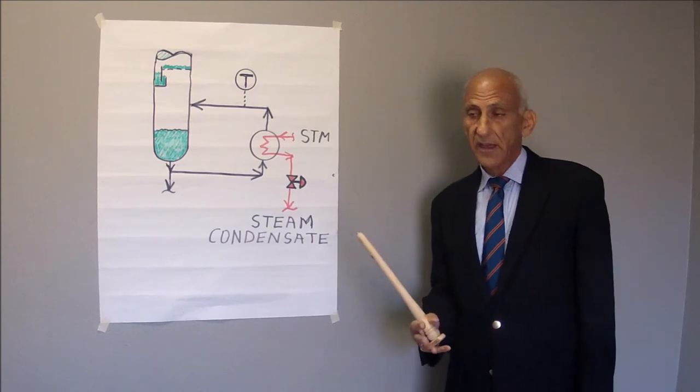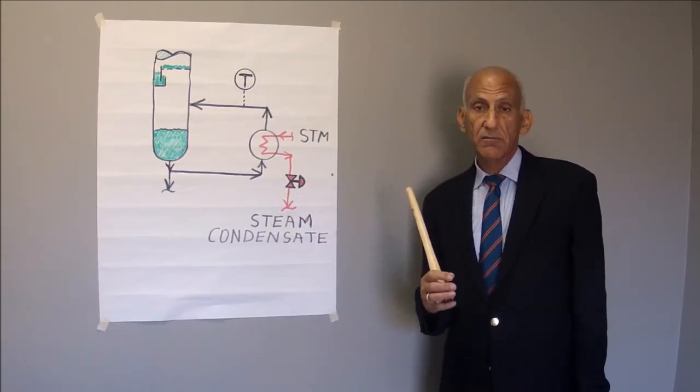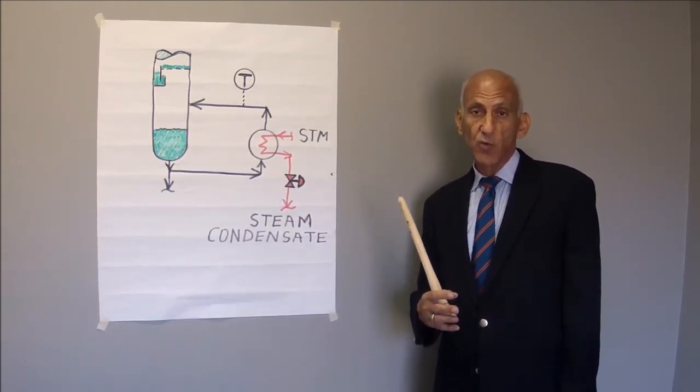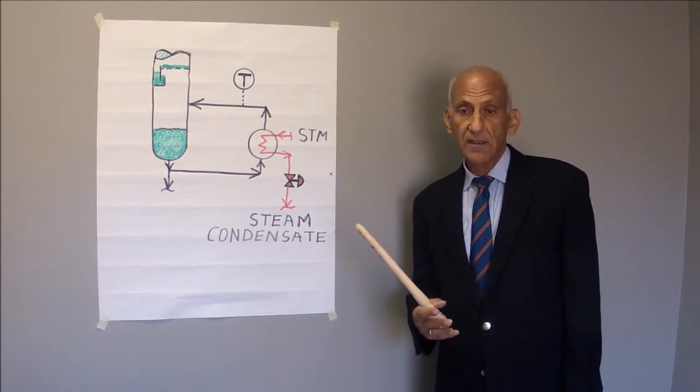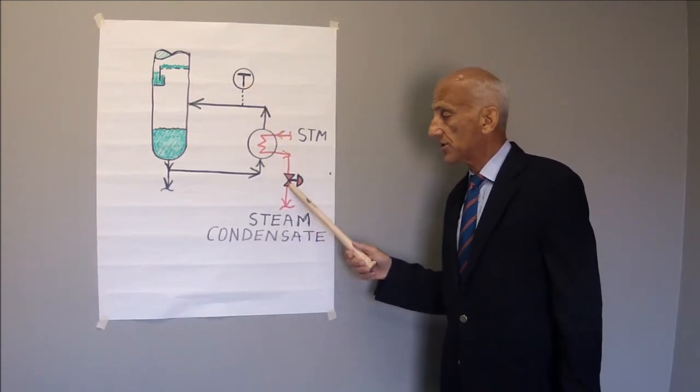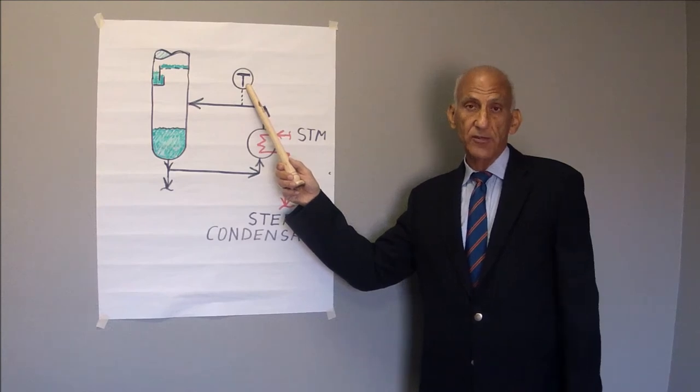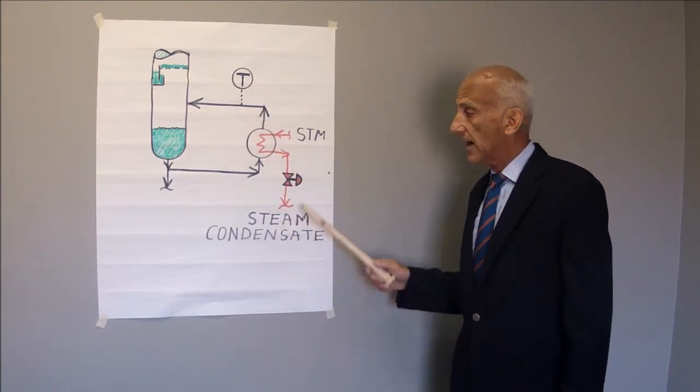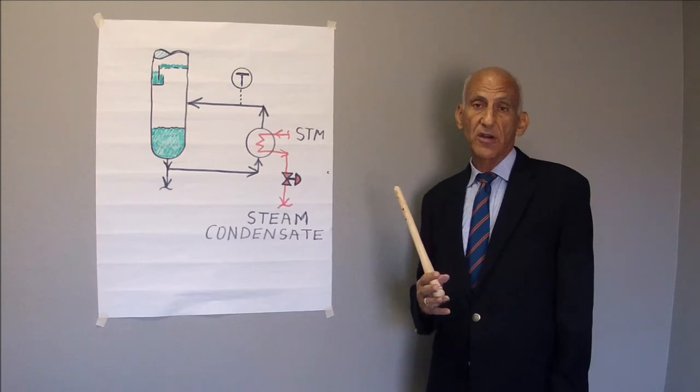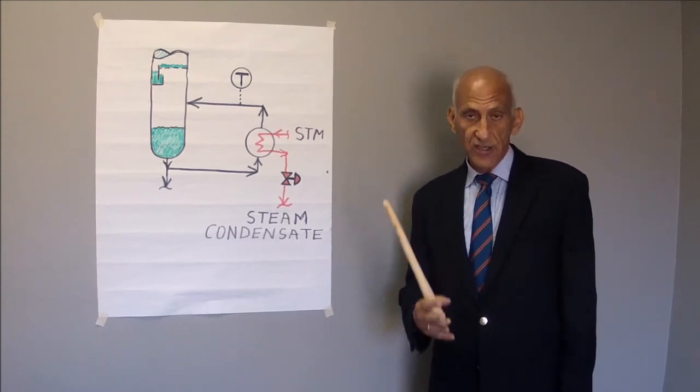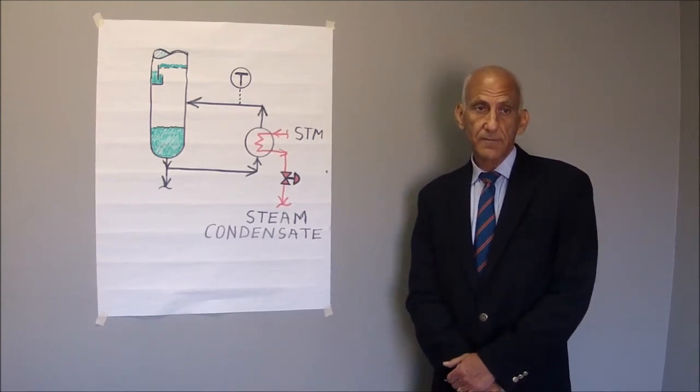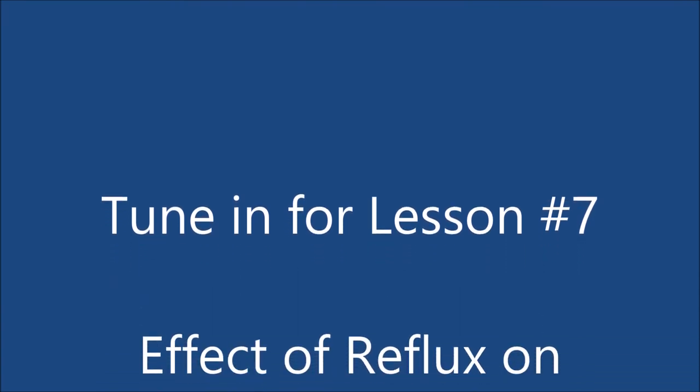On the other hand, if you close the valve too much and promote condensate backup and sub-cool the condensate, closing this valve will also cause this temperature to drop. So the operator adjusts the condensate drain valve to maximize the reboiler shell side outlet temperature.